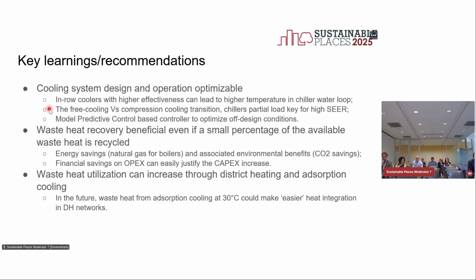Moreover, as we are adding a heat recovery system, we have to take care that instead of free cooling, we should take this heat and not give it to the air, but give it to the building BL26. So we have to play a little with it, and this way we can improve the seasonal energy efficiency ratio of the system.